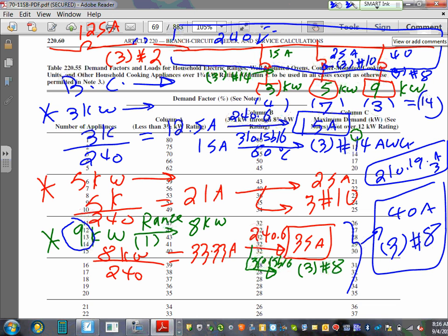But then if you go to 210.19(A)(3) exception, it will tell you that for ranges, especially ranges in a dwelling, you shall not use less than a 40 amp branch circuit. Here's my 40 amp branch circuit. Would the number 8 still be good for 40 amps? You go to Table 310.15(B)(16). Yep, number 8 is still good. Check, done. If that was number 10, then you have to up it to match the overcurrent protection device.